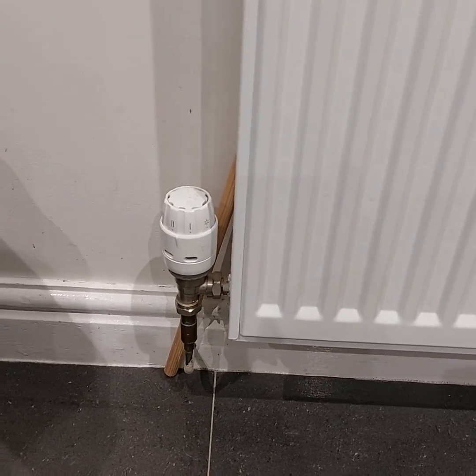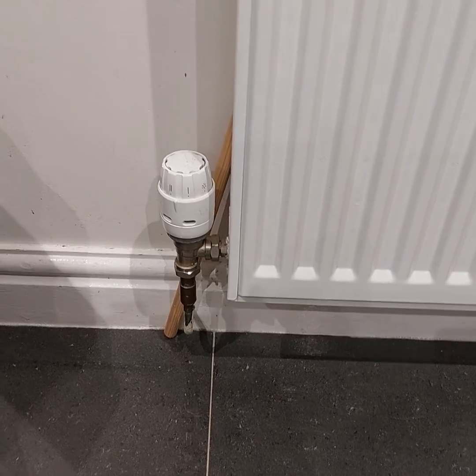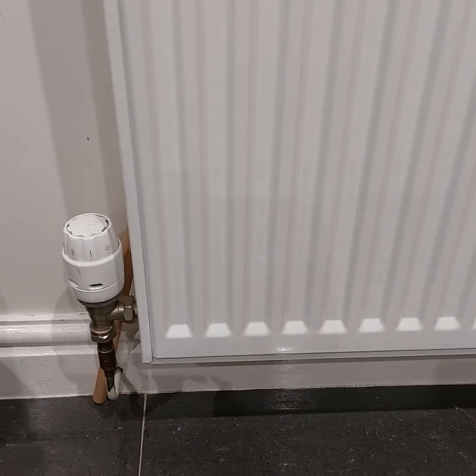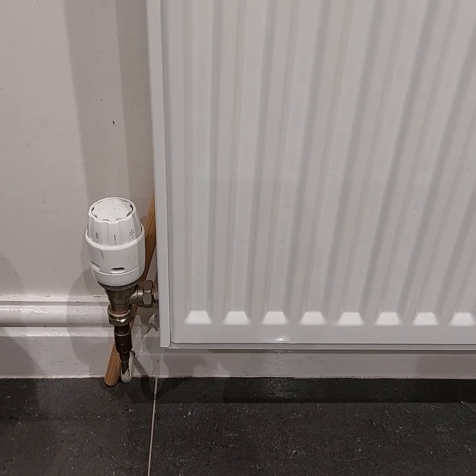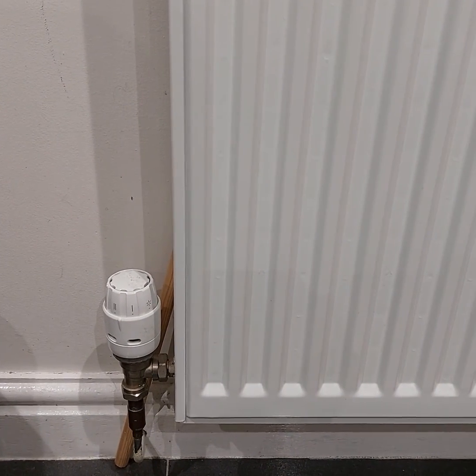The reason for that is to stop the heat pump from cycling too often. What you want is for the heat pump to run continuously at the set temperature — you want it not to overshoot by more than half a degree. So it's important to balance your radiators to achieve the temperature you want, whether that's 19, 20, or 21. The best way to do that is to use radiator balancing and to have the water temperature flowing through the radiators low enough — not too low, not too high — just enough so that it maintains the house at a constant temperature with the heat pump running as constantly as possible. That gives you the best running cost combined with efficiency.